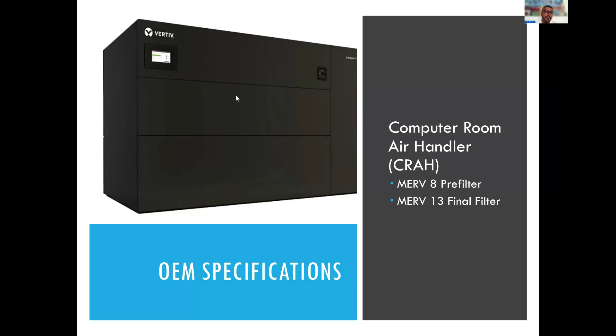For smaller IT rooms and smaller cabinet spaces, you'll find this in maybe smaller businesses that have a tech closet or something like that. They will come with an OEM washable filter. Typically, it should be replaced every 5 years. However, it should be checked every 3 months and washed every 3 to 6 months, depending on usage. We do not suggest replacing that filter with something else.